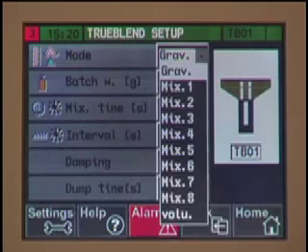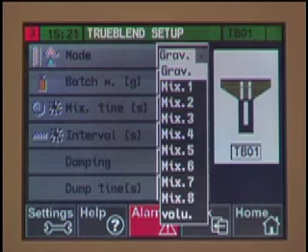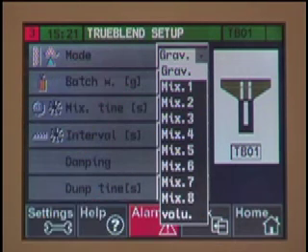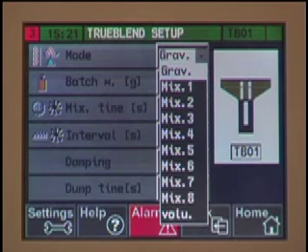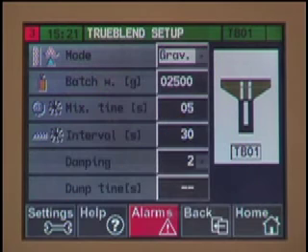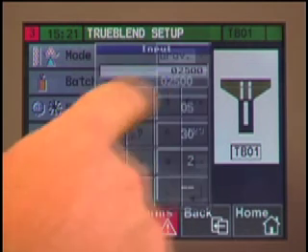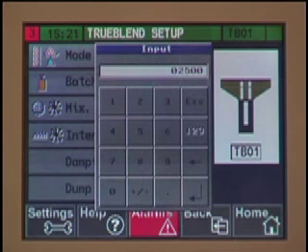The operating mode allows you to choose between gravimetric mode (default), volumetric mode, or a combination of the two. The combination can be helpful if the blender throughput requirement is higher than originally specified. The volumetric mode can be used if you have problems with a load cell. The batch weight is optimized for the blender model. On occasion, when running high percentages of light bulk density materials, it may be necessary to reduce batch weight to accommodate the larger volume of the lighter material.